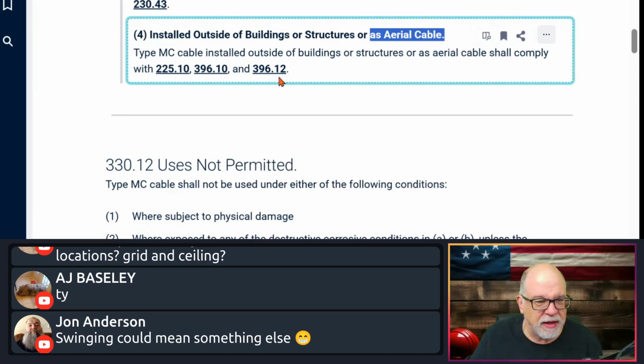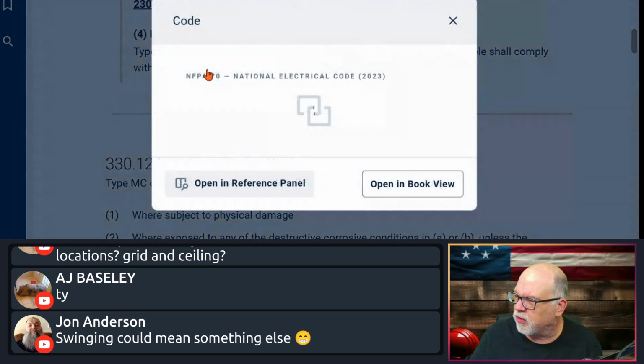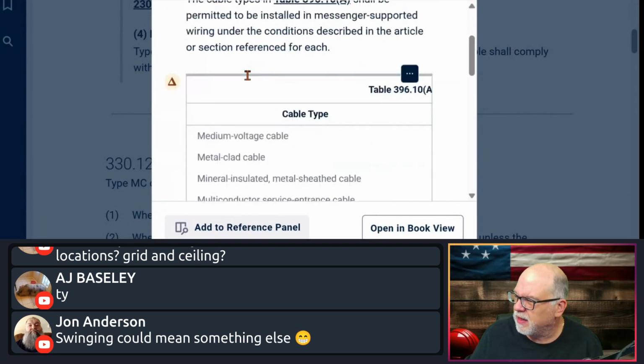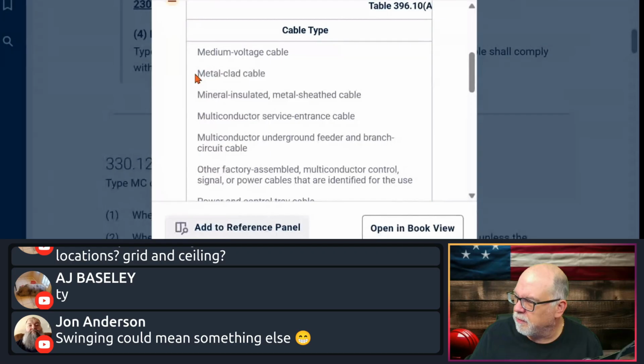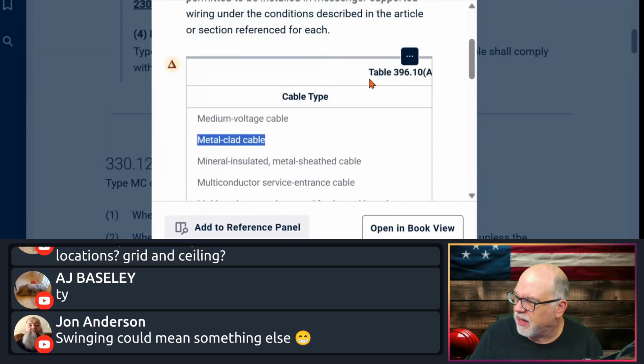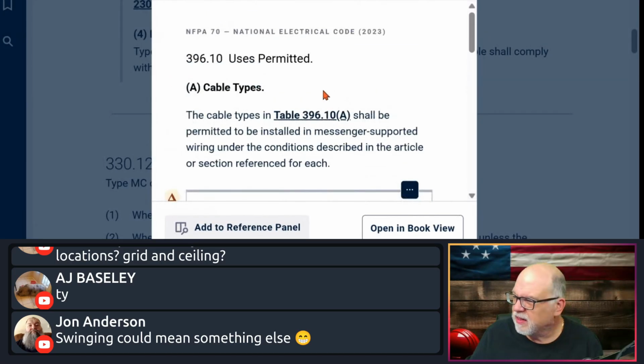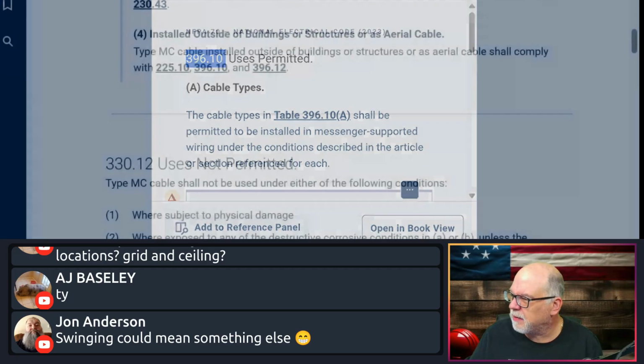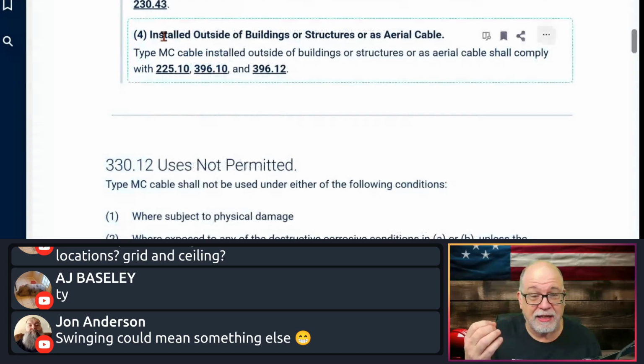And then you got uses permitted and uses not permitted. For example, I'll click on this one. Here's your uses permitted. And you'll see there's a list here. And you'll see that metal-clad is in this list of cables that are acceptable on a messenger. Still got to follow all the rules in 396, by the way. But at least it gets you started. You know that I could run an MC from point A to point B and support it on a messenger and be okay. And that may be your only option.